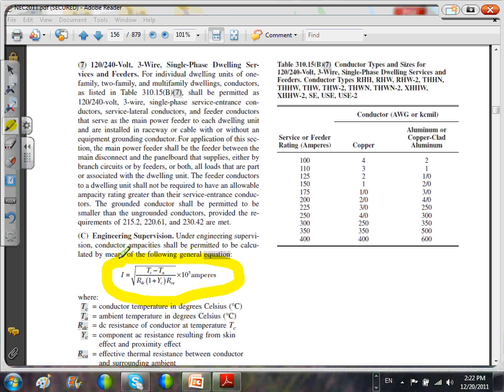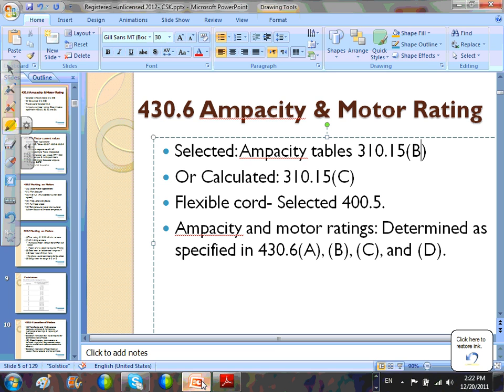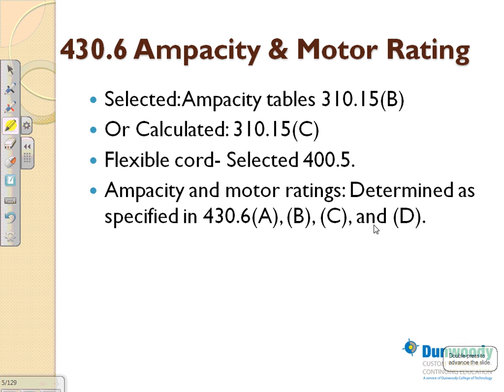That's where this becomes really interesting. So I thought just to highlight that one here, and if you're using flexible cords, which sometimes you have a bus duct, you tie from the bus duct with a flex cord, and you tie to the equipment, right, to a disconnect. You're going to go to table 400.5. So that's basically where we get all our conductors.